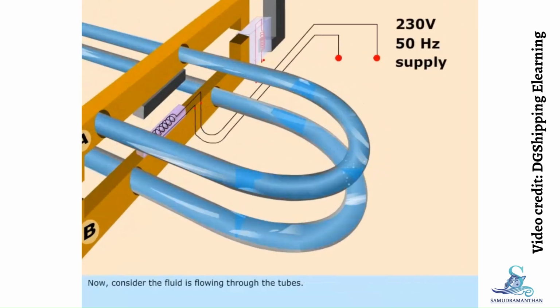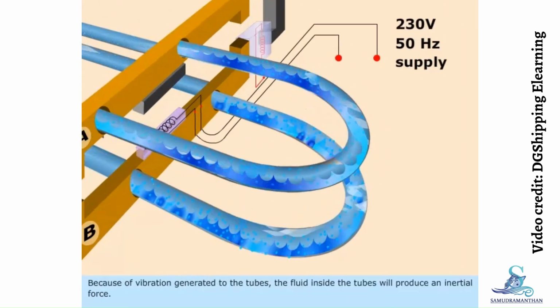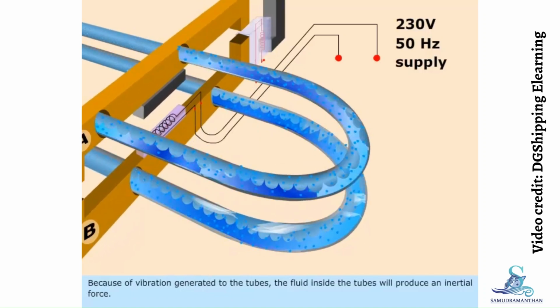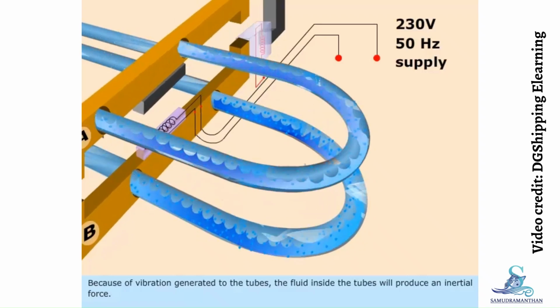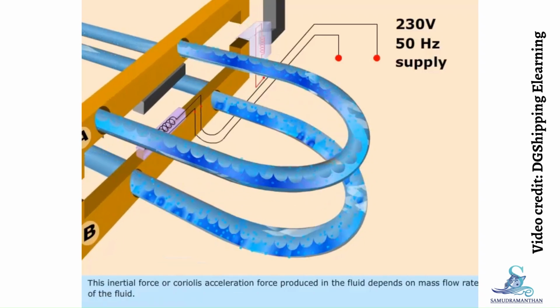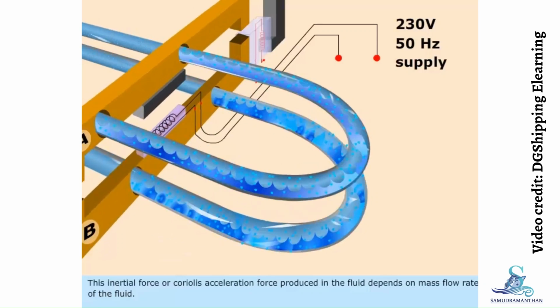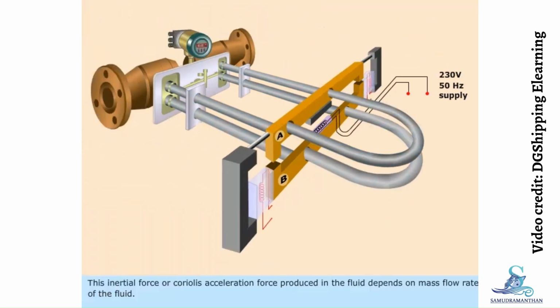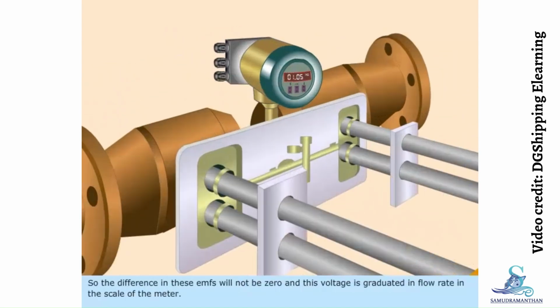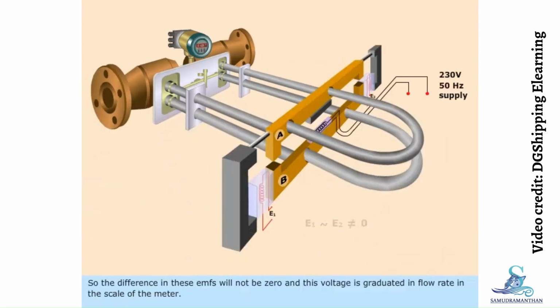Now, consider the fluid is flowing through the tubes. Because of the vibration generated in the tubes, the fluid inside the tubes will produce an inertial force. This inertial force, or Coriolis acceleration force, produced in the fluid depends on the mass flow rate of the fluid. This additional inertial force will cause different induced EMFs in the two sensing coils. So, the difference in these EMFs will not be zero, and this voltage is graduated in flow rate in the scale of the meter. In this way, we can measure the mass flow rate of the fluid. Thus, you have learned about the Coriolis mass flow meter.